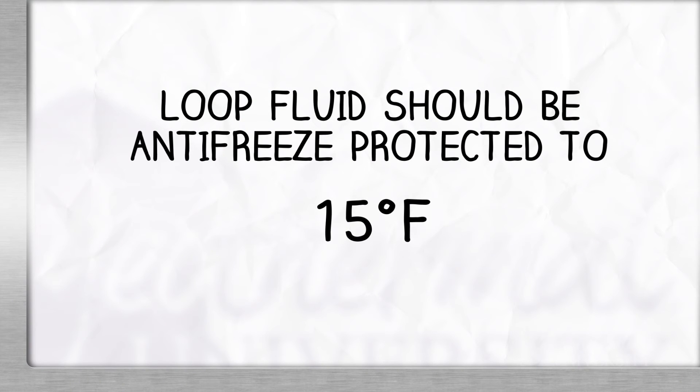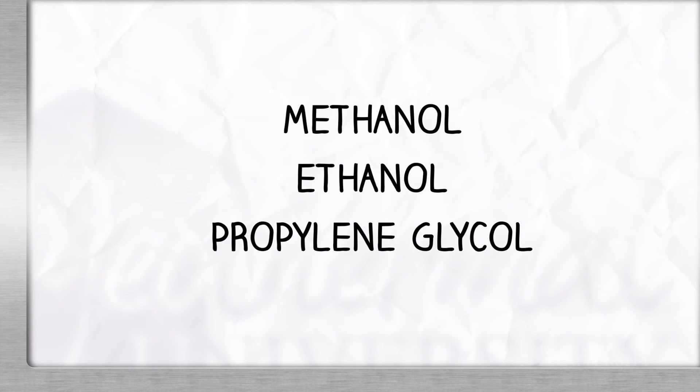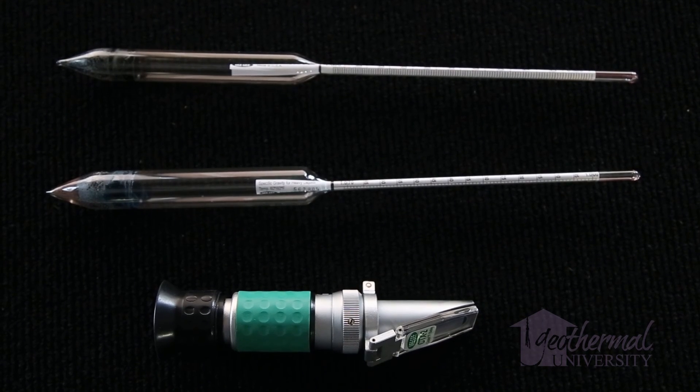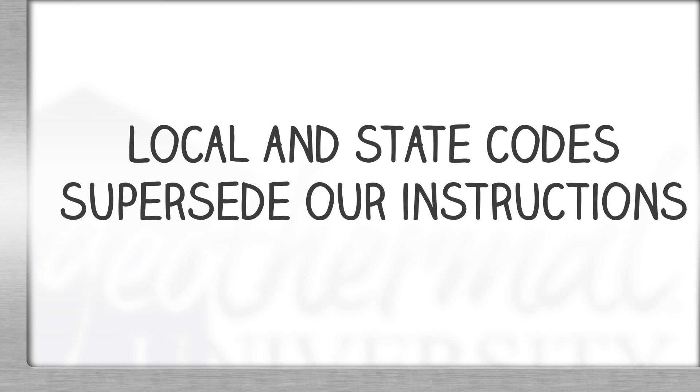Loop fluid should be antifreeze protected to 15 degrees with an approved fluid type, typically methanol, ethanol, or propylene glycol. Test with the proper hydrometer. Local and state codes supersede any instructions in this video or our installation guides.